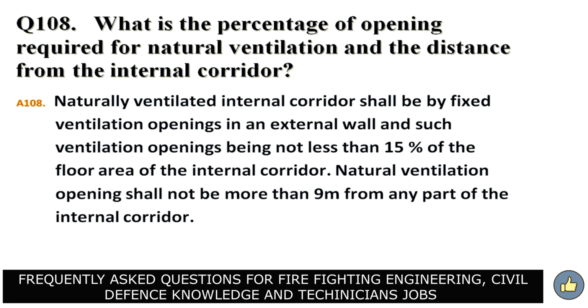Question number 108. What is the percentage of opening required for natural ventilation and the distance from the internal corridor? Answer. Naturally ventilated internal corridor shall be by fixed ventilation openings in an external wall, and such ventilation opening being not less than 15% of the floor area of the internal corridor. Natural ventilation opening shall not be more than 9 meters from any part of the internal corridor.